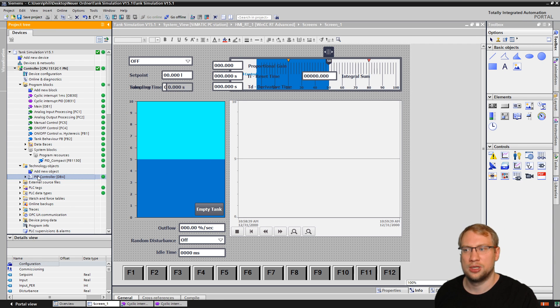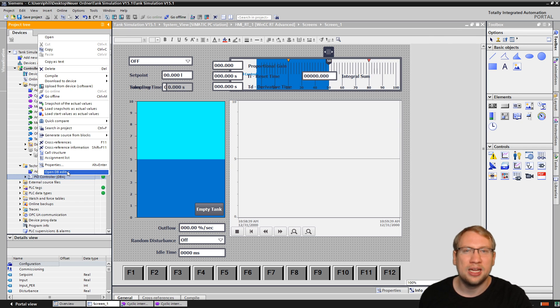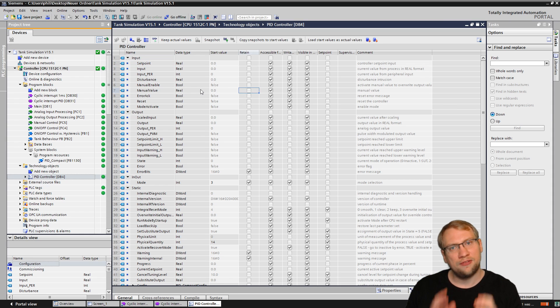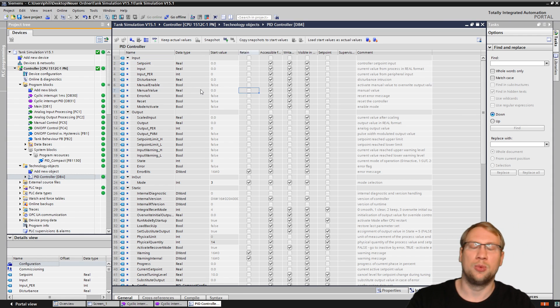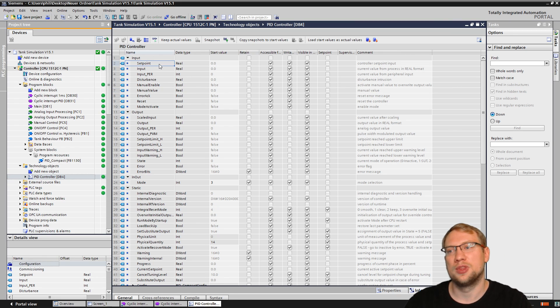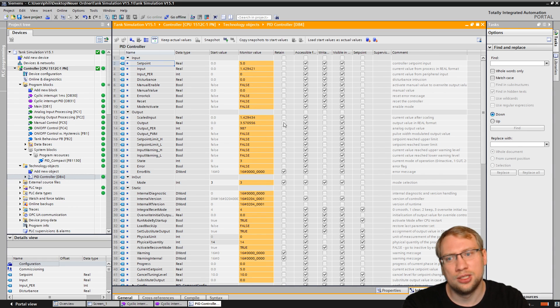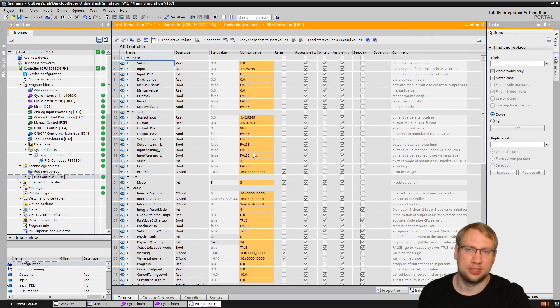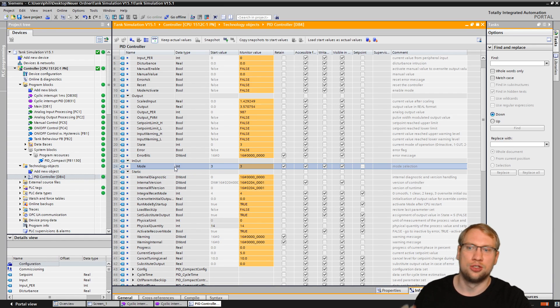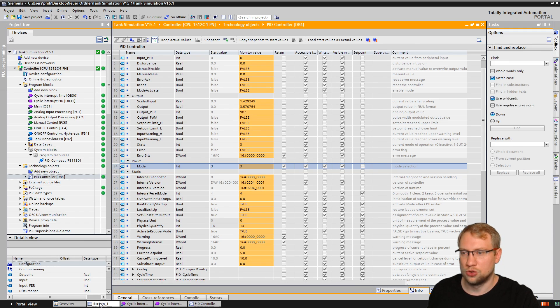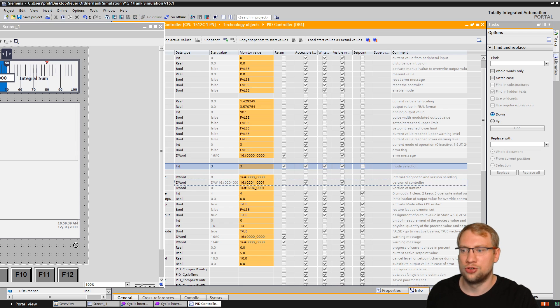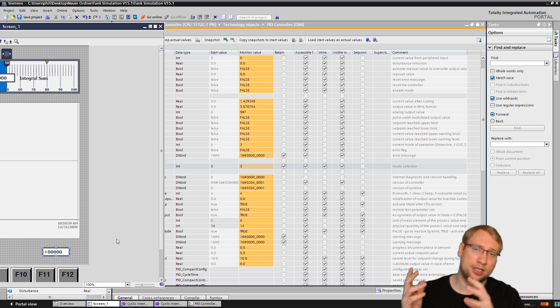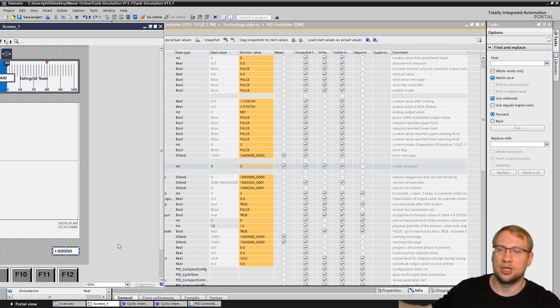So open the data block editor, and you will see the data block with every single entry that this, well not every single one, there's also internal ones, but with most variables and tags that the block uses. So if I go monitor all, you see internally there's a lot of calculations going on. We could right here change all of these parameters. I could, for example, change the mode here. So if I want to change the mode during runtime, what I can do is just take this mode, go to my screen. I could just take that mode, go to my screen here, just drag and drop that mode onto my screen. And now in runtime on the HMI, I can change the mode using that input here. I could make it pretty, but this video is not about making anything pretty. This is the mode.